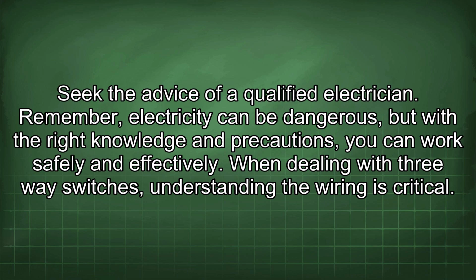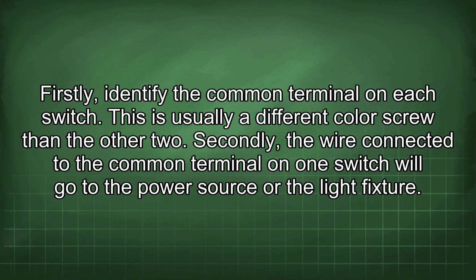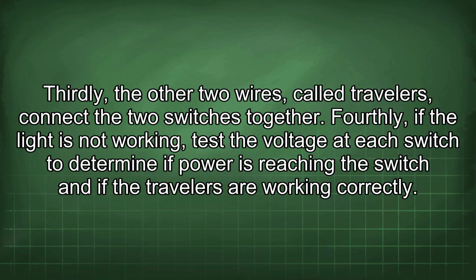When dealing with three-way switches, understanding the wiring is critical. Firstly, identify the common terminal on each switch. This is usually a different color screw than the other two. Secondly, the wire connected to the common terminal on one switch will go to the power source or the light fixture. Thirdly, the other two wires, called travelers, connect the two switches together.